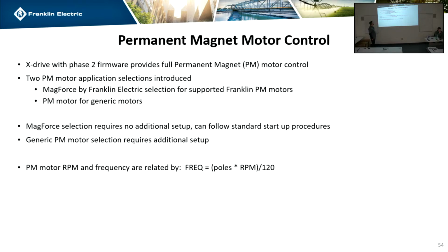So in the drive, you're going to see 2 options. You're going to see a MagForce option that's our motor, and then you're going to have a generic setting. The Franklin motor is very much plug and play. You just tell it what motor you have and you're good to go. The generic ones require a little bit more setup, but it's just like a regular motor. It just has more things you have to input. The permanent magnet motors are very particular. The drive has to know exactly where the motor is at all times, and it's just a lot more information that it has to deal with.